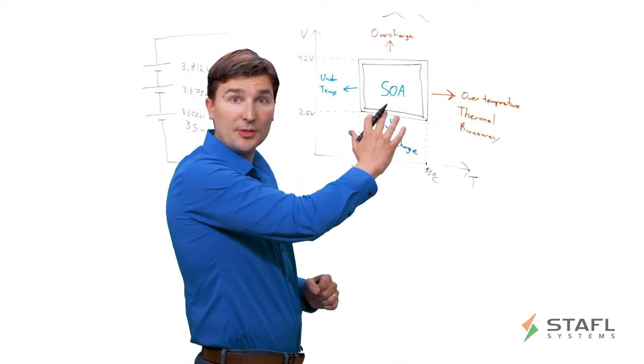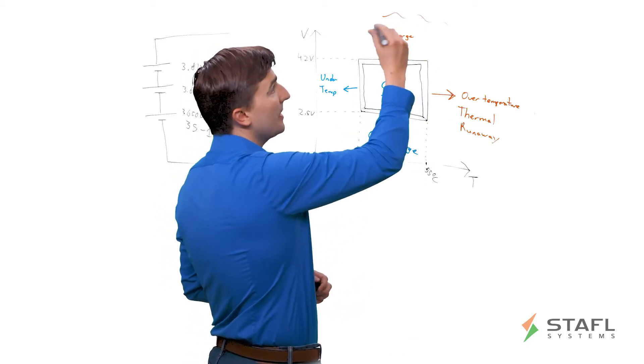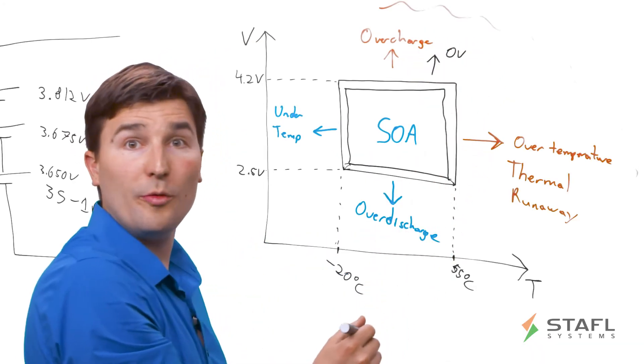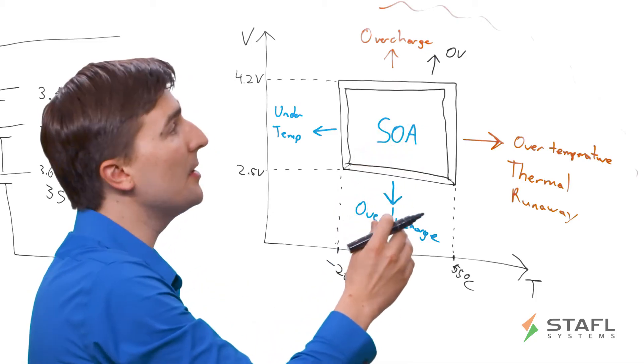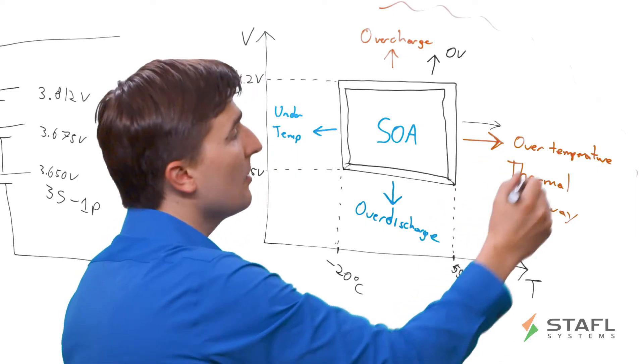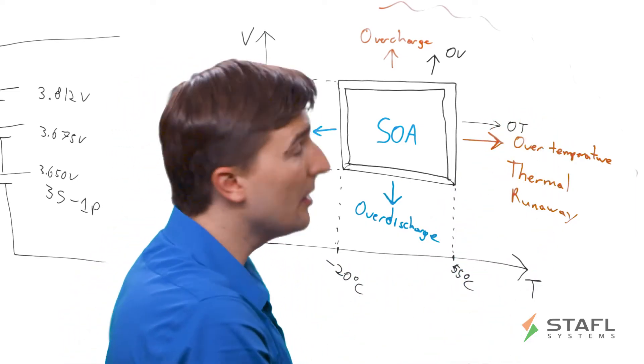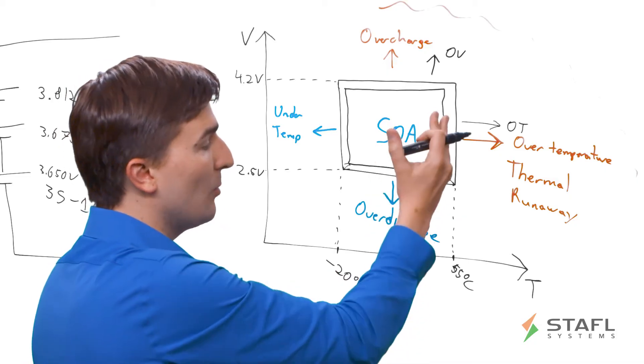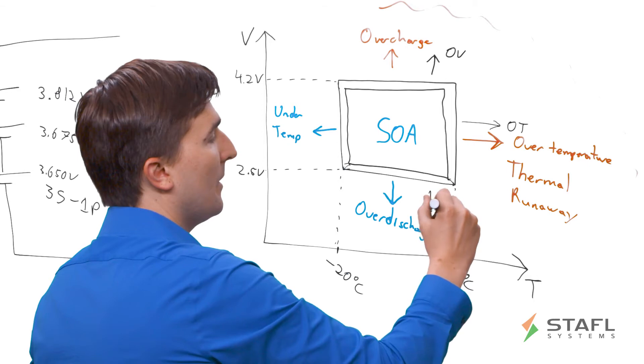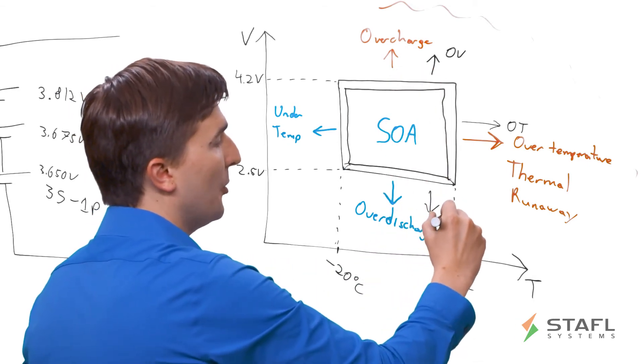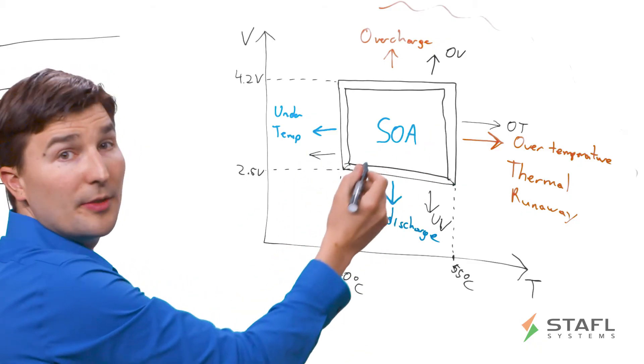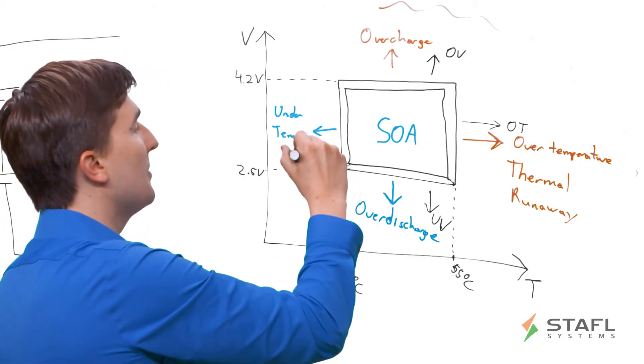And so what are the actual faults that the BMS is looking for? So to protect against the overcharged condition, we have an over-voltage fault or an OV fault. So you see a cell OV fault in the BMS that's protecting against this condition. This direction, we have an over-temperature fault or OT fault. So the BMS would detect that one or more cells are getting above a safe temperature and shut down operation. Going this direction, we have a cell under-voltage fault, denoted by UV. And then going this direction, we have a cell under-temperature fault, denoted by UT.